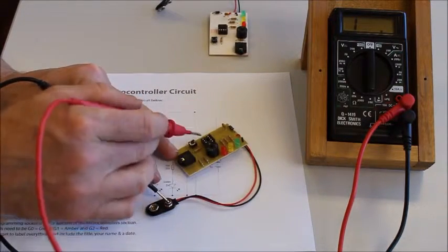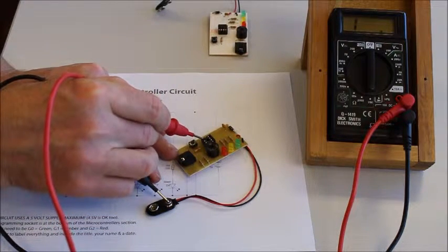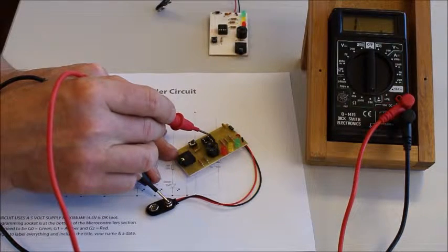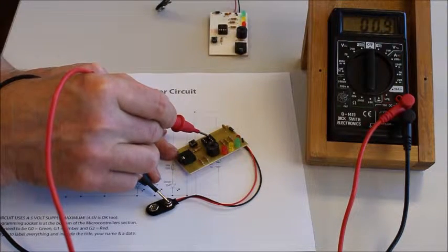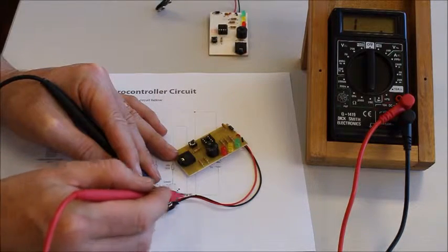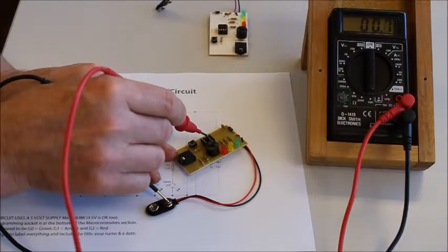I'm going to test on to pin 1 there and again we haven't got any shorts there. I'm also going to check on to pin 8 and there we've got a dead short which is what we're looking for because we're on the negative lead which should connect to here. So that is good.